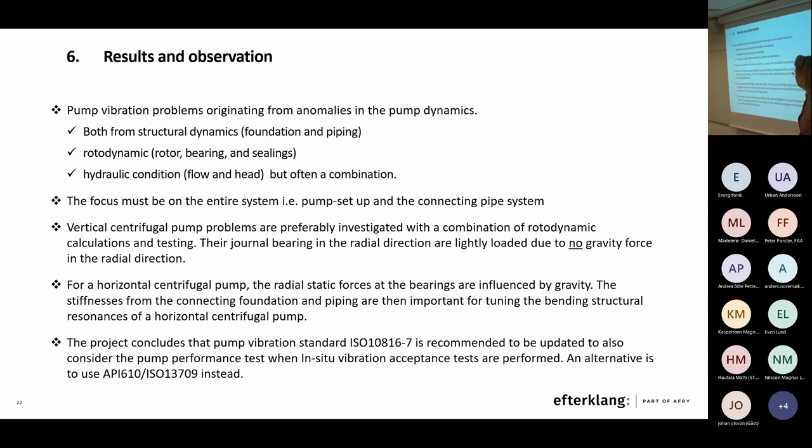If you have a multi-stage horizontal pump anyway, there you also need to have a rotodynamic calculation, because they contribute to the stiffnesses. The bearings and the sealings add stiffness or remove stiffness to the actual pump system. And this can also be complicated to calculate for the sealings. When you're talking about rotodynamic calculation, you often distinguish whether you have calculated it for a dry pump or a wet pump. And there are different models for how to deal with sealings and bearings or calculate the stiffnesses.